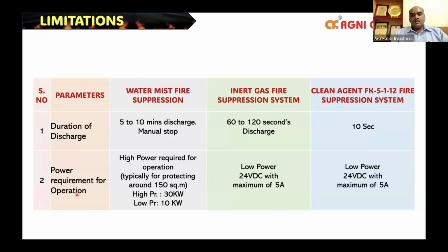Coming to the power requirement, pump-based water mist fire suppression systems require very high power. Typically, for protecting a 150 square meter area, we need 30 kilowatts for a high pressure system and 10 kilowatts of power for a low pressure system. Comparing that, the inert and the clean agent systems require only 24 volt DC power, with a maximum of 5 amps or even 10 amps based on the capacity of the risk area. But we require only a low power of 24 volt DC.